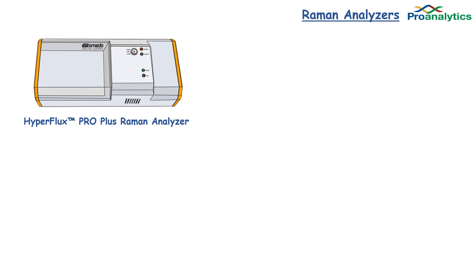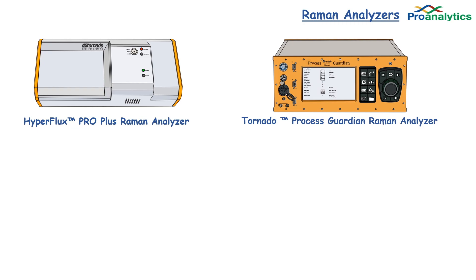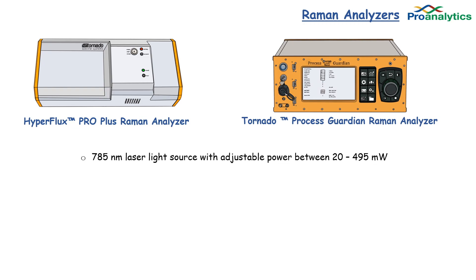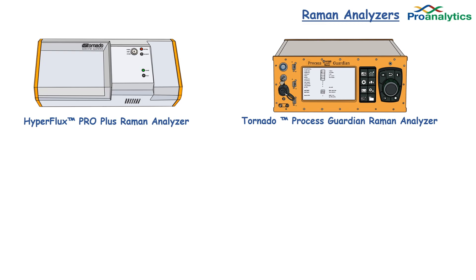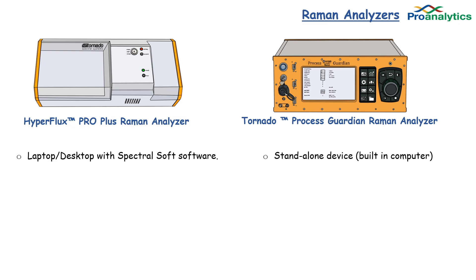Let's look at the Tornado equipment. The Tornado Hyperflux Pro Raman is on the left, and the Tornado Process Guardian is on the right. Both come with a 785 nanometer laser source that is adjustable between 20 and 495 milliwatts. Each takes measurements under 30 seconds and comes with Tornado's HTVS technology. Both instruments will pair with either the direct immersion or non-contact Raman probes. The Hyperflux Pro is run through a laptop with Spectral Soft software, and the Process Guardian is a standalone unit.